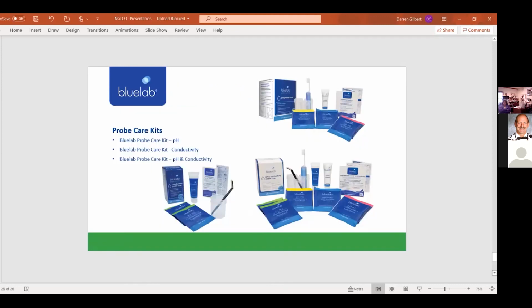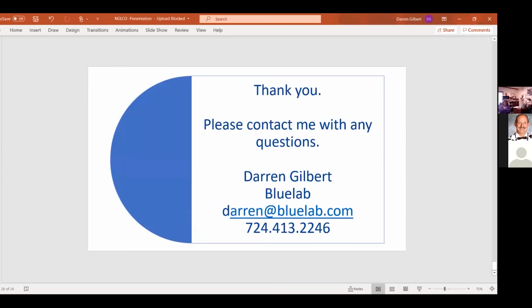We also have probe care kits for everything we manufacture, because you do need to calibrate. On average, it's about 30 days for everything but the pulse. The pulse, once it's calibrated, will hold calibration. A couple of our devices, like an EC pen or the truncheon, never need to be calibrated, they just need to be cleaned. The number one reason we see things coming back is because people don't clean their products, they just use them.